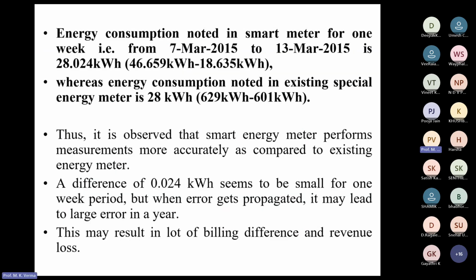The energy consumption noticed by the smart meter for 1 week was 28.024 kilowatt hours, and for the existing special energy meter it is 28 kilowatt hours. So you see, the smart meter detects a higher energy consumption by a small amount. This amount seems small for 1 week, but if you calculate for 365 days, you can see how much revenue the utility is going to lose if the measurements were performed by the conventional existing special energy meters.